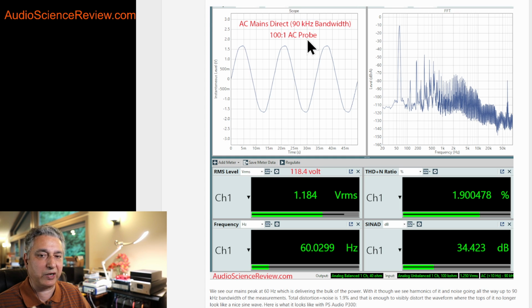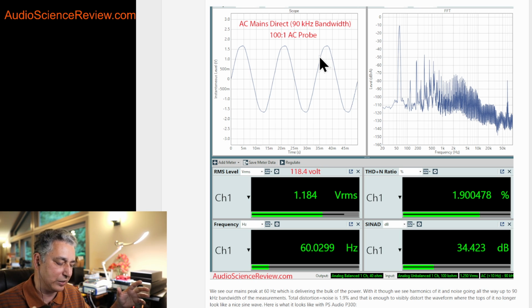The probe is also differential in nature. What that means is that any noise that lands on it, if it's the same on both cables, doesn't get amplified. And that's important because in our environment, there are other sources of AC noise and what have you. You want to really measure the device you're measuring as opposed to what could radiate onto it. So it does that also for us, which is very nice. And my Audio Precision has a differential input, so it all matches and works really well.